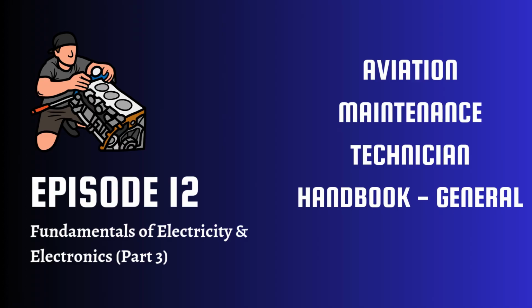Armature windings. They used to be a Gramme ring type. Yeah, an older design. The wires were wrapped around an iron ring. The problem was the wires on the inside of the ring were shielded from the main magnetic field and didn't cut much flux, so they didn't contribute much voltage. Kind of inefficient. So modern generators use the drum-type armature. The coils are laid into slots on the surface of a cylindrical core. This way, almost the entire length of the active conductor cuts through the magnetic field, making it much more efficient. Okay, now a big problem in DC generators.